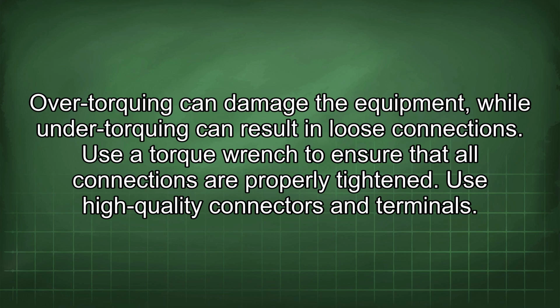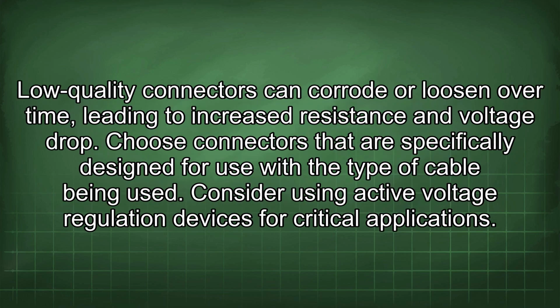Over-torquing can damage the equipment, while under-torquing can result in loose connections. Use a torque wrench to ensure that all connections are properly tightened. Use high-quality connectors and terminals. Low-quality connectors can corrode or loosen over time, leading to increased resistance and voltage drop. Choose connectors that are specifically designed for use with the type of cable being used.